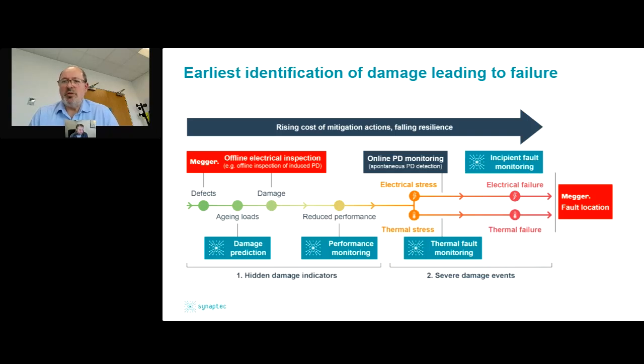So very important to stress that we would love to always install Greenlight and design it in before the cable is even built, while it's being installed, and during commissioning, so that we're ready to go as soon as it's energized. But because of the nature of the passive sensors that we use, you're able also to retrofit this system. So in the case of the customers that we've been talking to recently, this cable has already been installed for like 10 years, and the requirement is to see how long it will still be able to continue operationally despite some of these problems and these flooding events. And therefore, being able to retrofit this technology conveniently, safely, and fast is a major benefit.